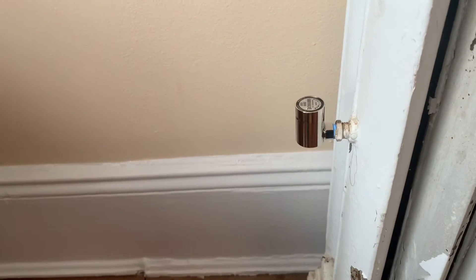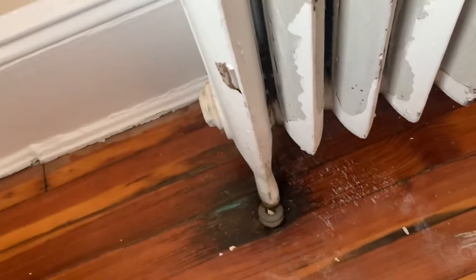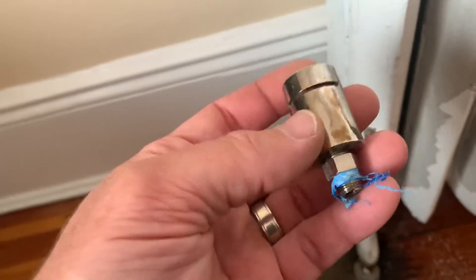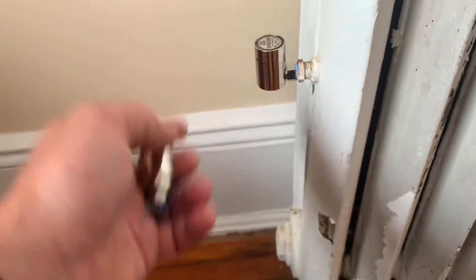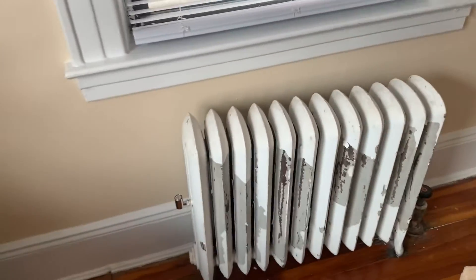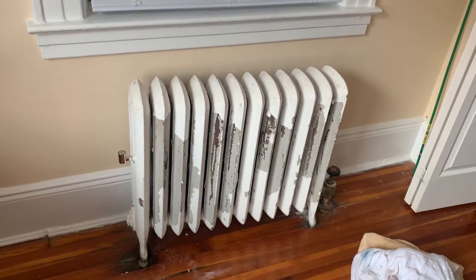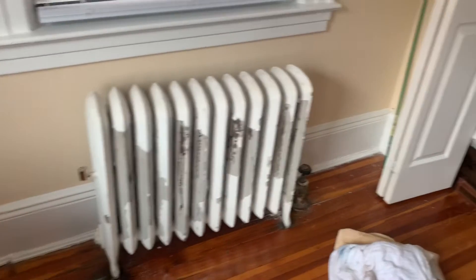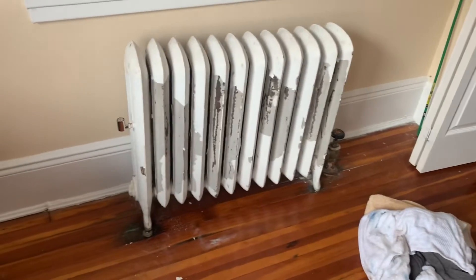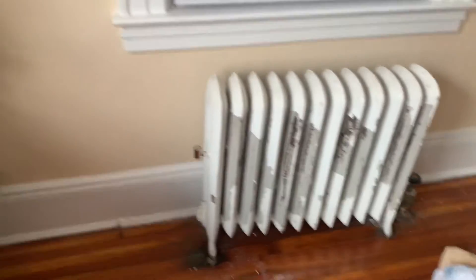This one wasn't in place but that one was. The straight one was in place, had a little street fitting in there, and this was spitting out water. At first, since it was coming out with pressure, I thought it had to be a clogged wet return — but no other radiator in this building is exhibiting that same problem.